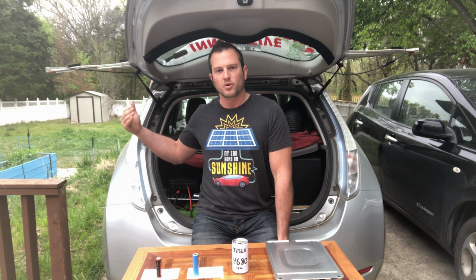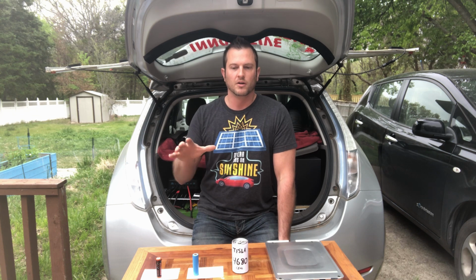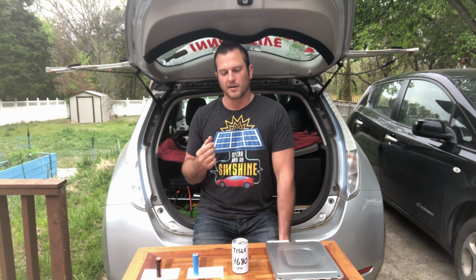We're having to move this power 50, 60, 70, 100 feet or more from where the solar is to the batteries. And the higher the voltage you transmit the power at, the less of it you lose to internal resistance in the wiring.